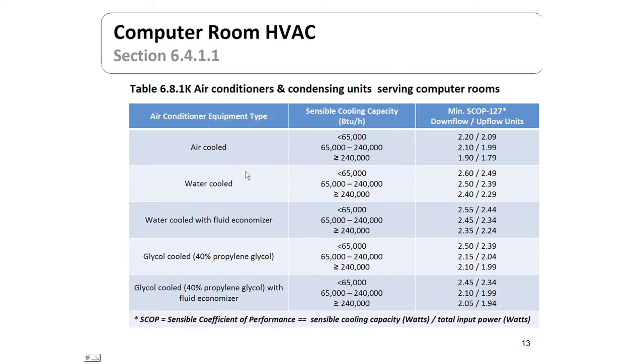For computer room HVAC, the requirements are specific and relate to the sensible coefficient of performance — not including the latent cooling capacity, just the sensible COP, which is BTUs of cooling versus the BTUs of energy put into the system. Equipment types covered include air-cooled, water-cooled, glycol-cooled, and others, with different efficiencies shown in the right-hand column.